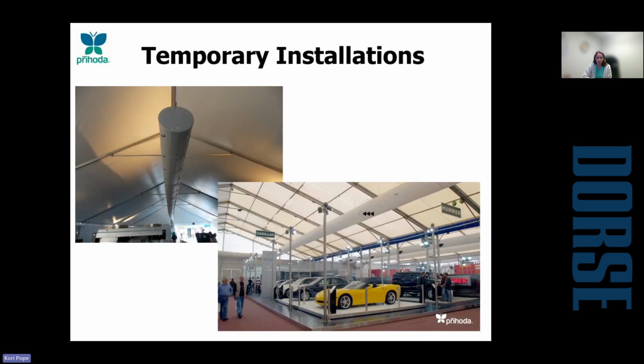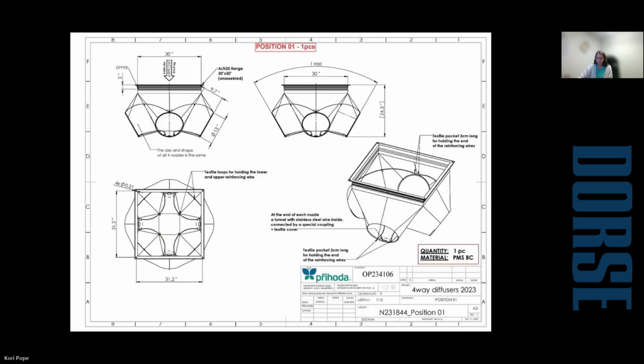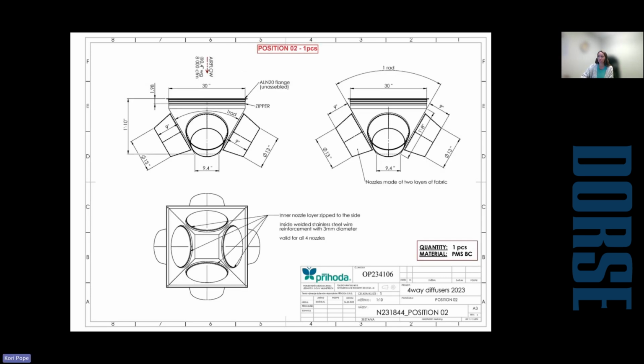Fabric duct is also great for your temporary applications because it is, again, lightweight and super easy to install. So I only have 2 more slides here, and this is going to be our latest and newest invention. This is a 4-way diffuser, fabric variation that we are going to call Omnitex. So this will work with that same aluminum snap frame that the SquareTex uses. Again, the sizes would be vastly different because these typically are much larger. But it'll have the same fabric face that you can unzip, stick down in a commercial washer, and wash it. And then you'll have your nozzles there for your 4-way, 2-way, 3-way, whatever way, how many nozzles you may need depending on the application.